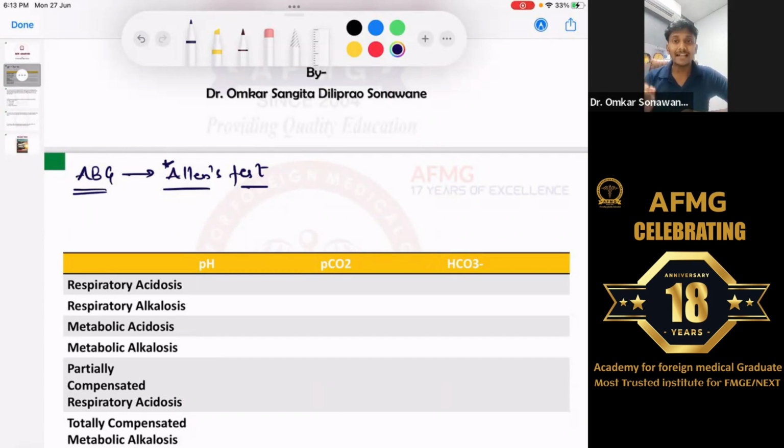Okay, and that syringe, you will not directly take a blood sample like you take a venous sample, because this is an arterial sample and there is a high probability or a propensity that this arterial blood sample will clot. Okay, and this clotted sample will not give you results, or that will lead to errors usually in the report. So that is the reason why before you take the sample, this 2 ml or 5 ml syringe is to be heparinized.